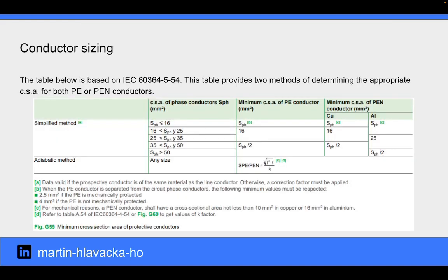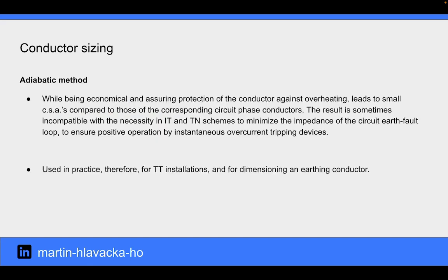Conductor sizing. The table below is based on IEC 60364-5-54. This table provides two methods of determining the appropriate CSA for both PE and PEN conductors. The first method is adiabatic. This method, while being economical and assuring protection of the conductor against overheating, leads to small CSAs compared to those of the corresponding circuit phase conductors.